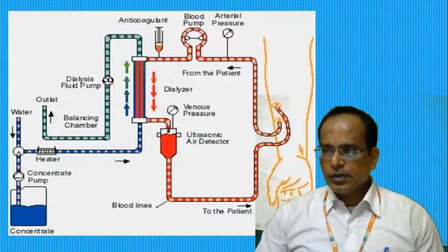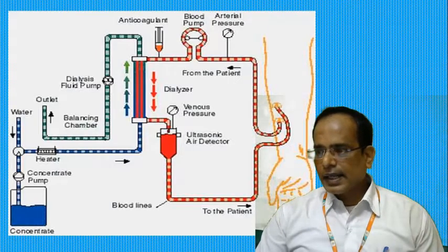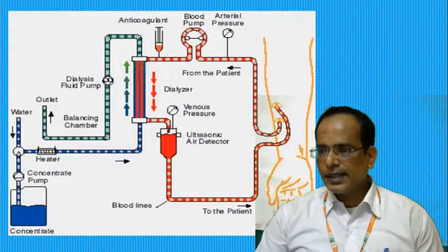These alarms turn on and give a beeping sound, and similarly they turn off the machine as well as alert the staff of an impending catastrophe. That is very important. There are also temperature regulators and controls provided here.